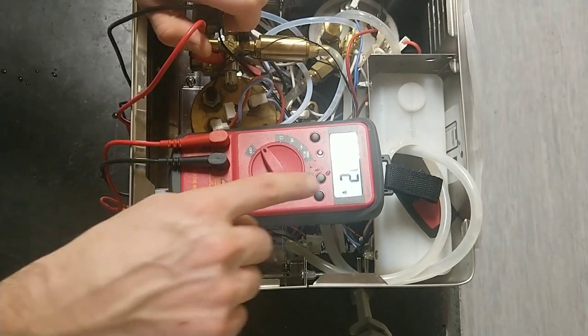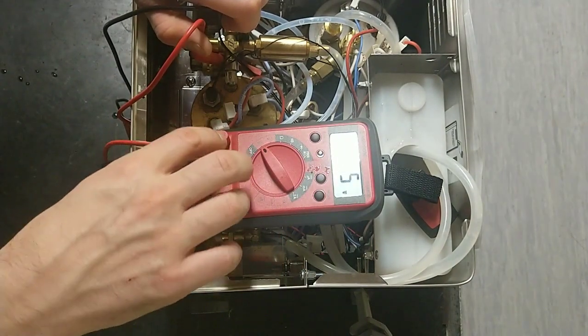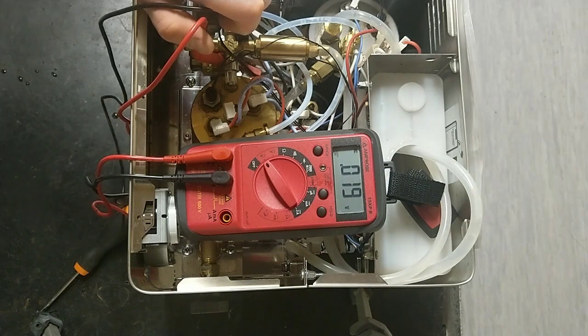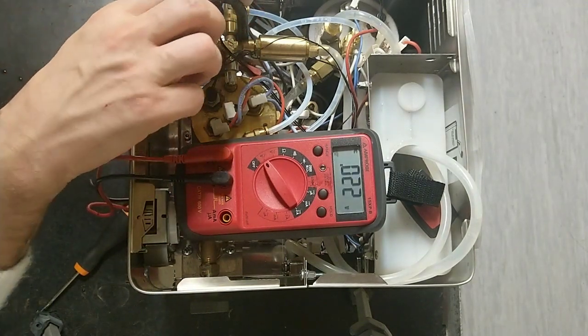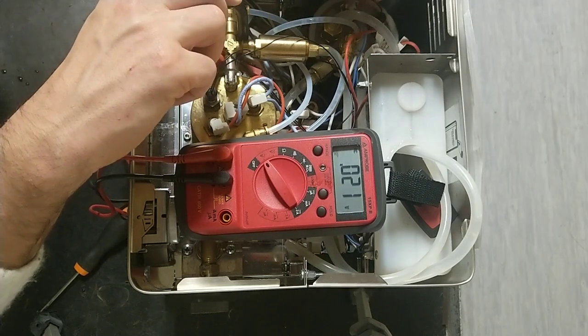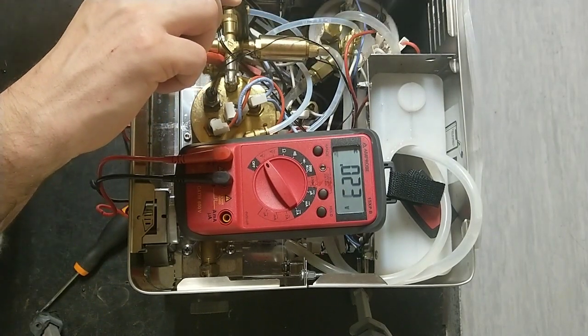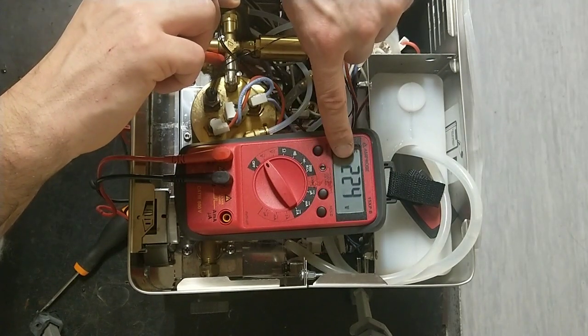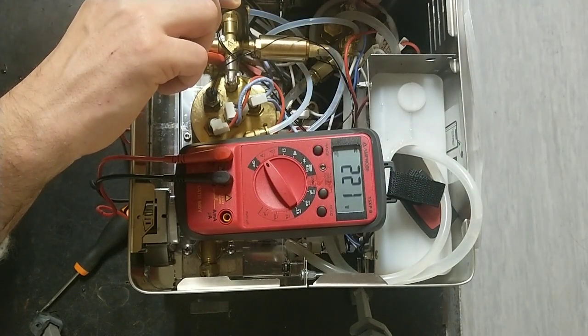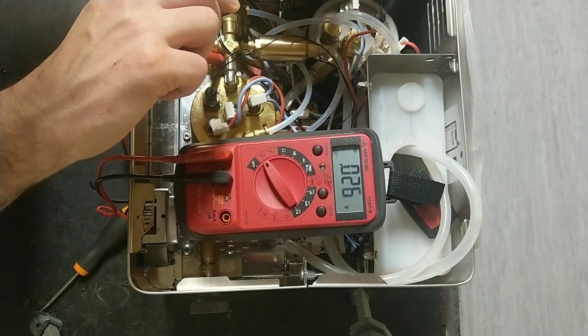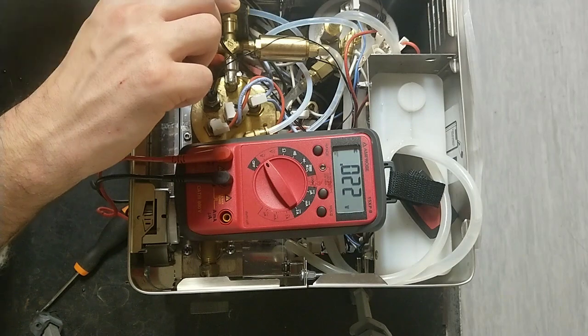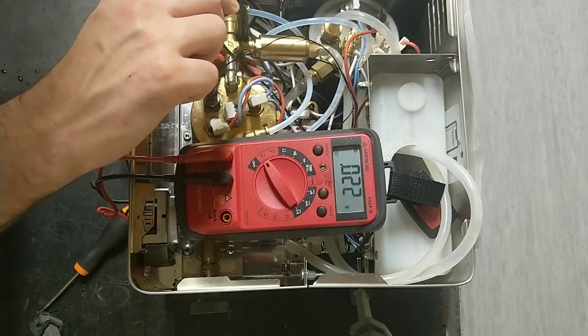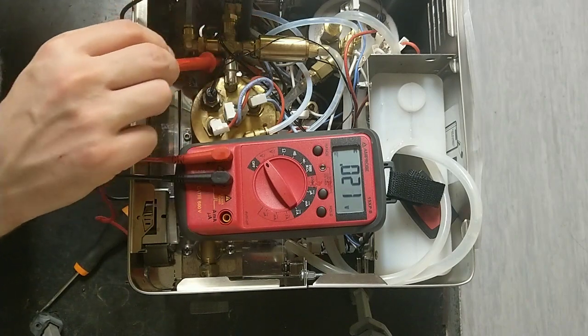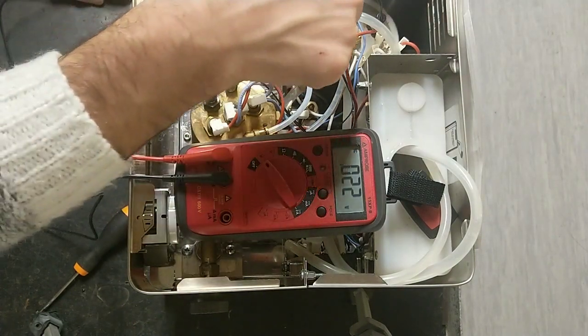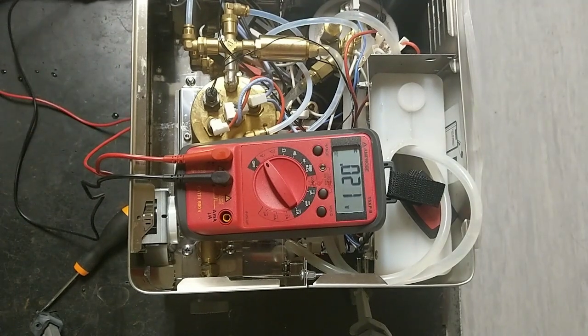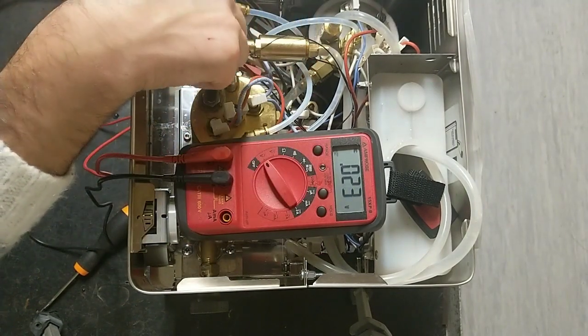Okay, check. It is 220 volt. This means that, for example, if I remove this wire, the wire from the water level probe, I can see 220 volt. It means that the pump is running and the two-way water charge solenoid valve is open. And then if we have a problem here, we have to check if this valve receives power.